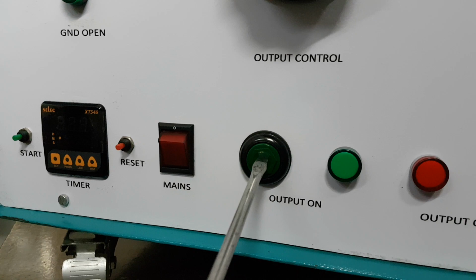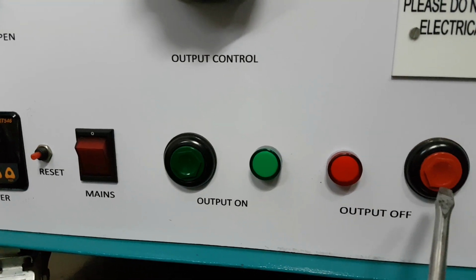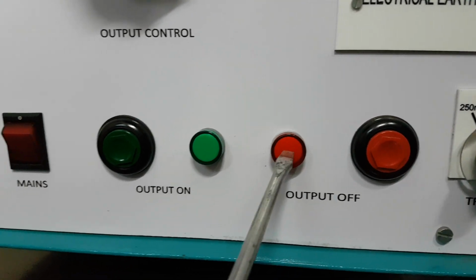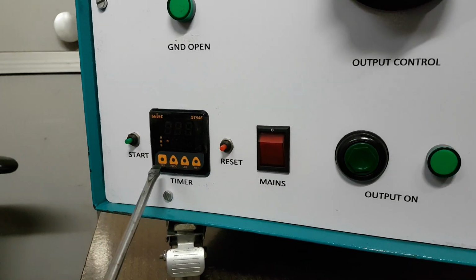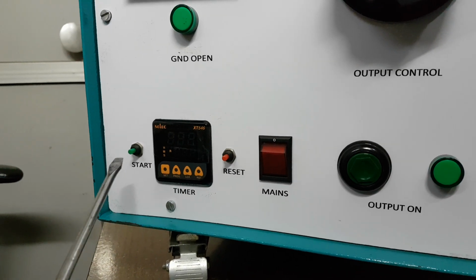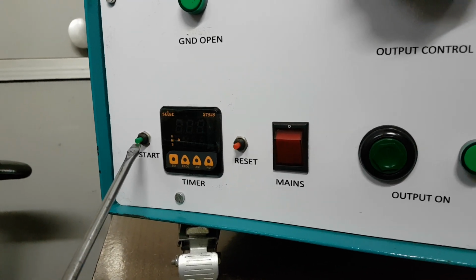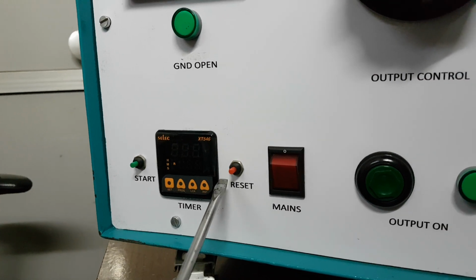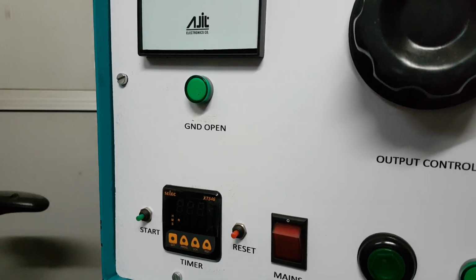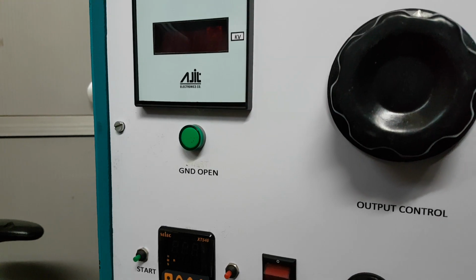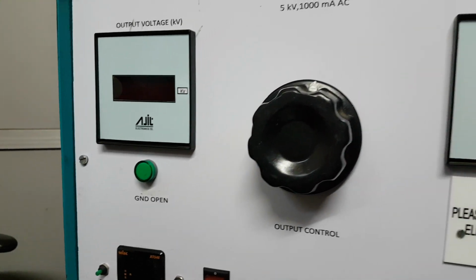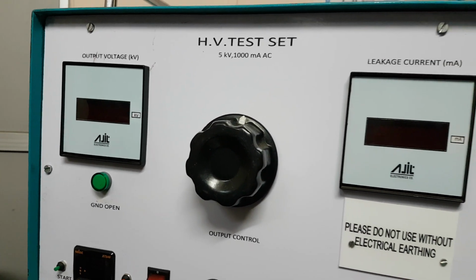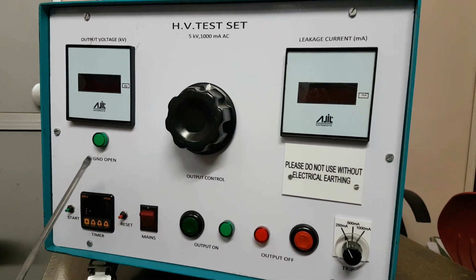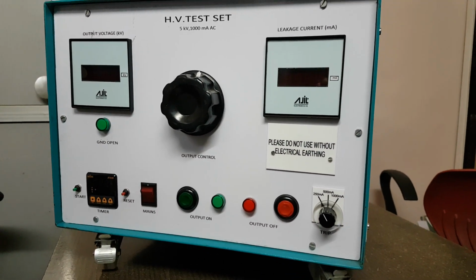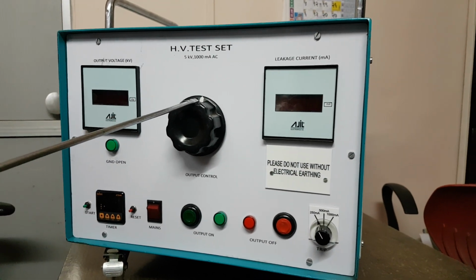This is output on button, output on lamp, output off push button, output off lamp. Here there is a timer, that is test duration can be set on the timer. This is the timer start button and this is the timer reset button. This is an indicator. It comes on when the electrical earthing or the ground is not connected properly. Once the ground is connected properly, this lamp goes off. This is the output voltage controller, as I said.